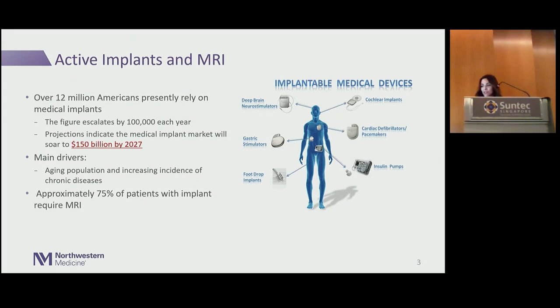Now, a little bit of MR physics, which I'm sure everybody knows about. Let's think about what could potentially go wrong when we put a patient with a conductive piece of metal in an MRI machine. There are three fields that we should be worried about: the static field, the gradient field, and the RF field. In this talk, I'm talking about what we call active implantable medical devices, or AIMDs. So these are electronic devices. I'm not talking about orthopedic implants. Most modern AIMDs have a very negligible amount of ferromagnetic material, so force and torque is not something that you are terribly concerned about.